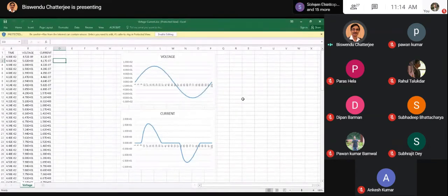The Excel contains the time, voltage and the current data. Once you have done this, exactly this thing is done in the metering system with the help of analog to digital converter. The circuit and the simulation, the input, etc. are done automatically because the current is received in the meter through a current transformer called the CT, and the voltage is directly fed to the meter through a potential divider. I think you know what is potential divider, R1 R2 division.